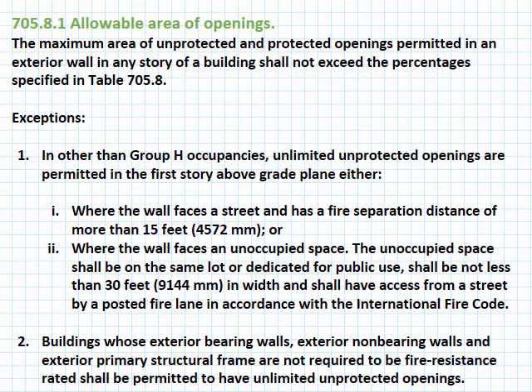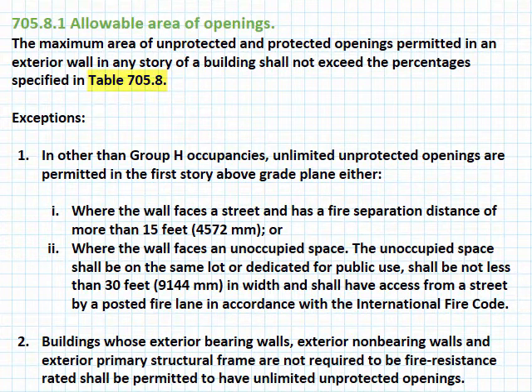The allowable area of openings on exterior walls is governed by IBC Section 705.8.1, which refers the code user to Table 705.8 for the maximum area percentages of exterior walls in any story that can contain either protected or unprotected openings. Section 705.8.1 contains a number of exceptions. Exception 2 permits an unlimited number of unprotected openings where the exterior non-bearing walls and exterior primary structural frame are not required to be fire resistance rated.